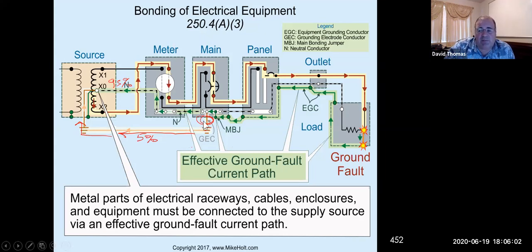But if you're working on these, you need to be very aware of the fact that some of the current does flow to Earth. The dirt itself is not a good conductor, so the current would rather flow on the green wire back to the source than through the Earth. But 5% of 100 amps is 5 amps, enough to kill you. Remember, anything above 50 milliamps can actually hurt you, or 1/20th of an amp can cause fibrillation of the heart, which means your heart's not going to be pumping correctly, and it starts shutting down your system, your blood flow to your brain. So we're not talking about that much current.